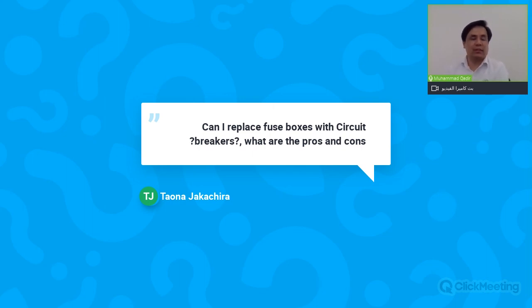If you have this query, I would say that with Huawei inverters, you do not actually need fuses, because we are connecting two strings to each of the independent MPPTs. If one of the strings doesn't work, the working string will have a reverse current of maximum 10 ampere, which is within the limits of the non-functioning string. Thus, there will be no damage to the non-working string due to the backfeed current. So no fuse box is required, and all the strings will be directly terminated to the Huawei inverter.